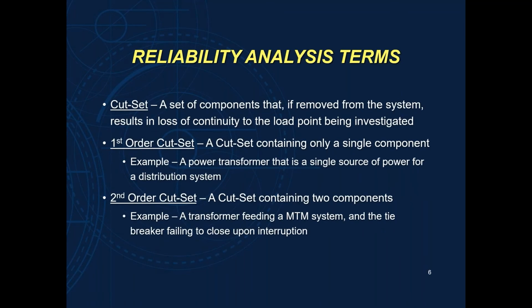So what we do per the Gold Book in order to determine the reliability or availability of a system is we're going to follow this cut set method. It's called the minimal cut set method. Essentially, a cut set can either be a component or a system of components or any collection of components that if you remove that set or that component from your system, you're going to lose your load. So you can have multiple types of cut sets. You can have multiple orders of cut set. So we're going to talk about first order. A first order cut set is a single component.